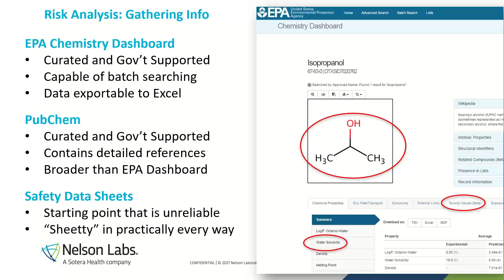So now that you have walked through all your research, identified your potential contaminants, and categorized those contaminants according to solubility, the next step is test selection. There are all kinds of choices which could be made at this point. We're going to stick pretty closely to the outline in ISO 19227. This is primarily a non-specific and quantitative approach, like NVR, TOC, and THC, which we'll get into. And it matches the typical recommendations that we've been making for many, many years. But it's worth noting that ISO 19227 is not absolutely strict with test selection. It emphasizes a risk-based approach and allows for alternative test method selections with justification.